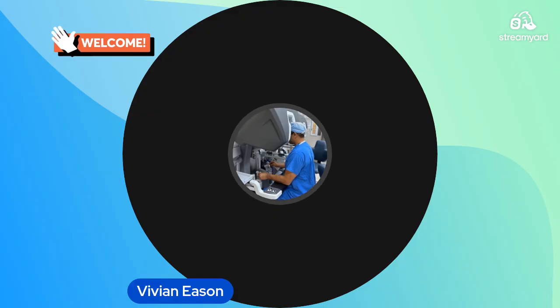Once the instruments reach decontamination, they must be processed according to the appropriate IFU. This may involve specific cleaning techniques, flushing, brushing, disassembly, or other manufacturer required steps. The important point is that cleaning must be effective before sterilization occurs. Sterilization is not a substitute for proper cleaning. If organic material remains on an instrument, it can interfere with the overall sterilization process. This is why sterile processing professionals need to pay close attention to the design of robotic instruments and the manufacturer's validated cleaning instructions.